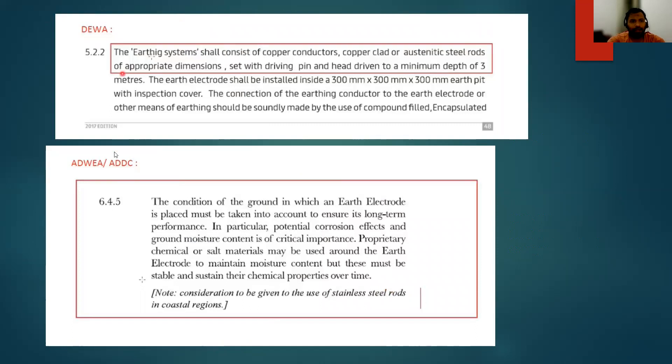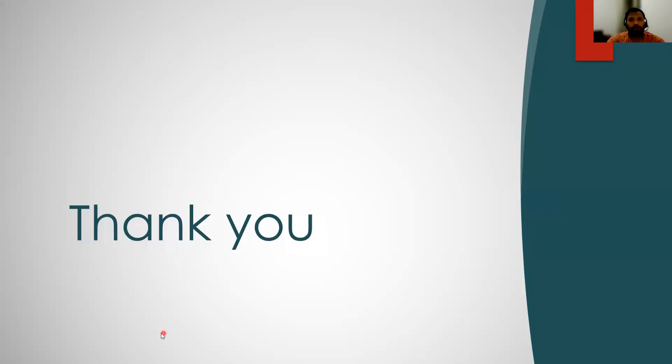According to the DEWA and ADDC standards, it says that if you are using the stainless steel rods, it is good. Earthing system shall consist of copper conductors, copper clad, austenitic steel rods. According to DEWA and ADDC as well as other standards, it will allow you to use stainless steel rods. Comparing all those parameters, if you are going for stainless steel, it will reduce your cost. Comparing to copper, stainless steel rods are very cheap. Overall, your system will be less costly.